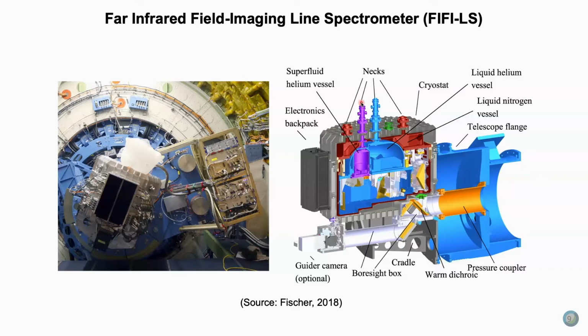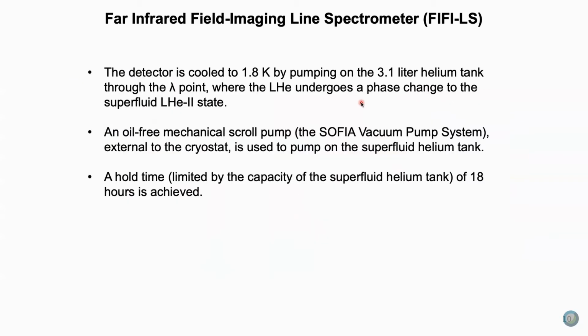But it has a second liquid helium vessel. And when it's operating, it's being pumped on. And when you pump on helium, or any liquid for that matter, it cools down. So in this way, the detector can be cooled to around 1.8 Kelvin, pumping on that 3.1 liter helium tank. And it becomes superfluid, but it's really the temperature that we're concerned about.